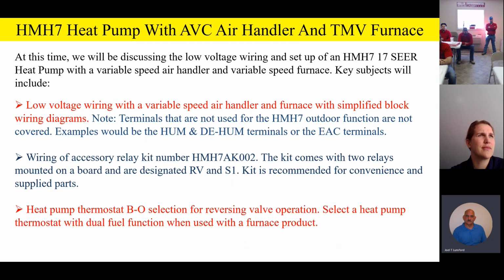So guys, if we get into the variable speed, like an AVC air handler, which is the older style air handler, or a TMV type of furnace, we're going to go through this block wiring diagram again. One of the things I would like you to notice: we're not going to talk about the humidifier and dehumidifier terminals. For simplicity, we're going to keep these block wiring diagrams simple. But just remember, on the variable speed product, you're going to have a dehumidification terminal, a humidifier terminal, and an electronic air cleaner terminal, and all that stuff that you can utilize those components. So we're going to be focusing on the relay setup as well as the low voltage wiring.